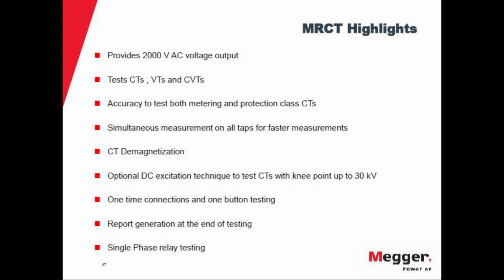For the concurrent testing here, you can see a CT with five taps. Everything is connected to the instrument on the secondary side and the primary side. And once you start the test, it will do all of the taps at the same time, concurrently. So you get all of your results in a very short time.